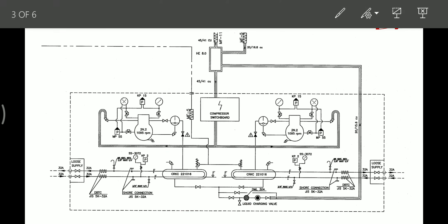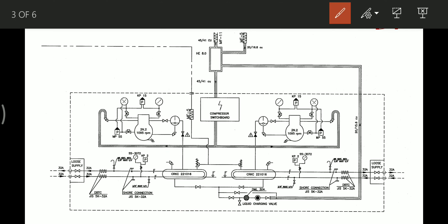This is the compressor. It takes suction from the line coming from the evaporator. It takes suction and discharges the refrigerant through an oil separator. This oil separator returns the oil back to the compressor, and the refrigerant gas is sent to the condenser.